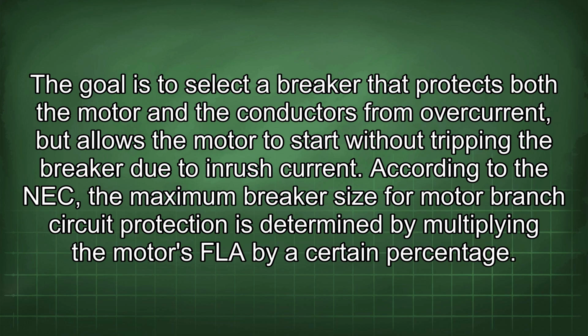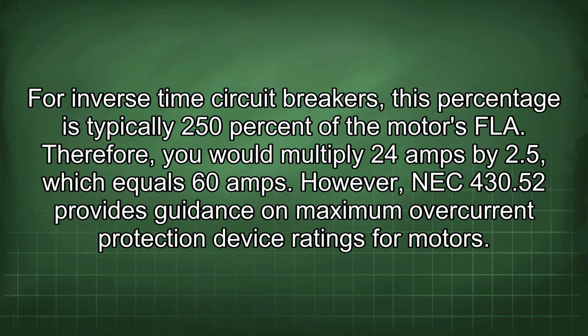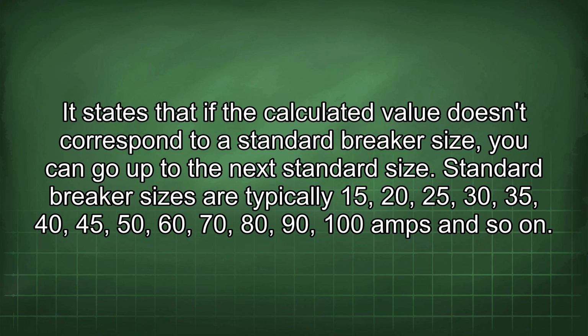According to the NEC, the maximum breaker size for motor branch circuit protection is determined by multiplying the motor's FLA by a certain percentage. For inverse time circuit breakers, this percentage is typically 250% of the motor's FLA. Therefore, you would multiply 24 amps by 2.5, which equals 60 amps. However, NEC 430.52 provides guidance on maximum overcurrent protection device ratings for motors. It states that if the calculated value doesn't correspond to a standard breaker size, you can go up to the next standard size. Standard breaker sizes are typically 15, 20, 25, 30, 35, 40, 45, 50, 60, 70, 80, 90, 100 amps and so on.